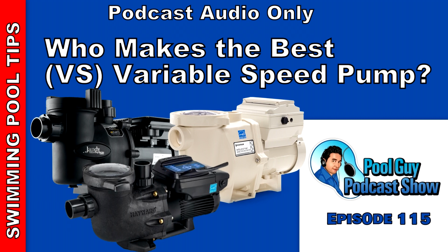The voltage of the variable speed pumps requires the 230 volts or the double breaker, and a lot of people have the older homes where they're running on 110 volts and they have the single 120 volt breaker at their panel. So the SuperFlo pump or the Hayward TriStar VS950 will work with an older pool setup that's running on a lower voltage. And so to recap, Pentair definitely makes great variable speed pumps, the IntelliFlo VS and the SuperFlo VS.